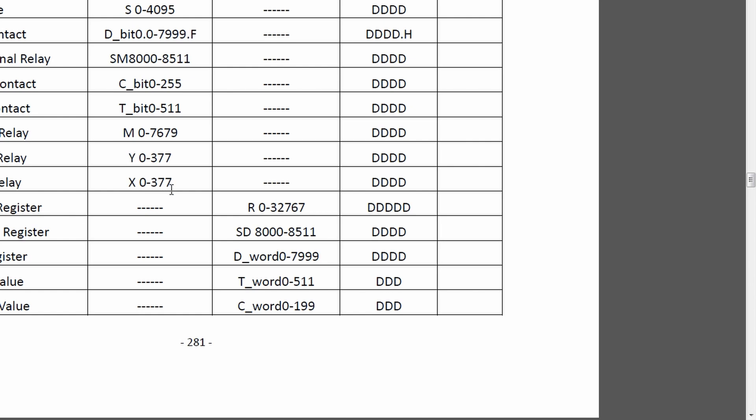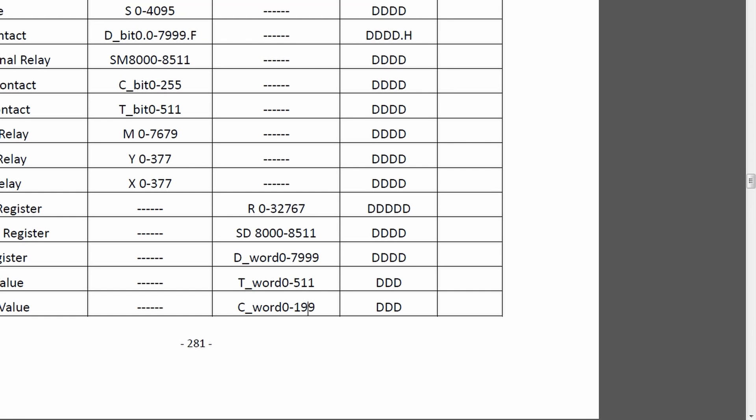There are counter values. There's timer values. I know that the FX series Ethernet has counters that go up to 255, but those are double words. These ones will only support a single word counter. So you can see that all these ones are mapped this way. If I need to be able to know if my state is on or off, you can apply a button and that PLC is going to map that button state from the PLC as a displayed contact on the HMI.